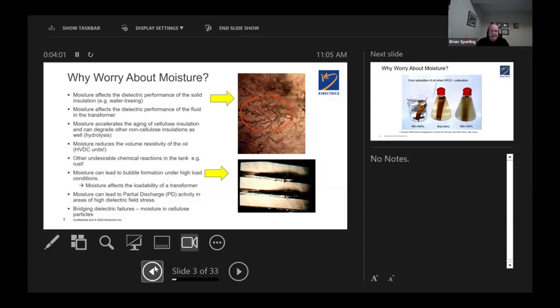But moisture affects the dielectric performance of the solid insulation. And in the picture there you see the pretty pictures of partial discharge across the surface, in this case of wet pressboard materials. That's typically between the low and high voltage windings and at the ends of the windings, around the curving of the coils. This is the evidence that the pressboard is wet, and this is partial discharge that is set up. It does not get better as it ages. It can degrade other non-cellulose insulations in the transformer by means of hydrolysis.